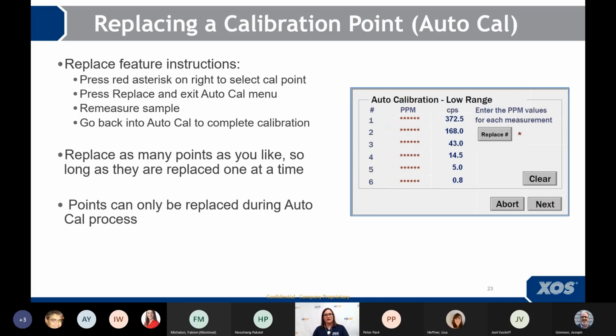Okay, so this is a very handy feature, because previously people thought you would have to rerun all of your calibration standards. And I'm here to tell you, you don't have to do that. Use the replace feature as often and replace as many of the points as you want, so long as you do it one at a time. And note that this replace feature can only be used during the AutoCal process.